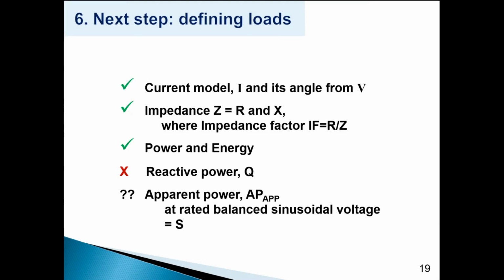So let's look at what we can and cannot do. We can take a current model and we can use current and voltage and the angle between the currents and voltages, and we can separate it into the frequency components, which are then sinusoidal signals, and that is completely acceptable. We can measure impedance. Impedance is a scalar. Z is made up of resistance and reactance at whatever frequency you choose, and you can define an impedance factor, which is R over Z. And if you look at that, it looks curiously like the factor which we call power factor, conventional power factor. And so maybe there's not such a difference there when you're looking at impedances and currents.